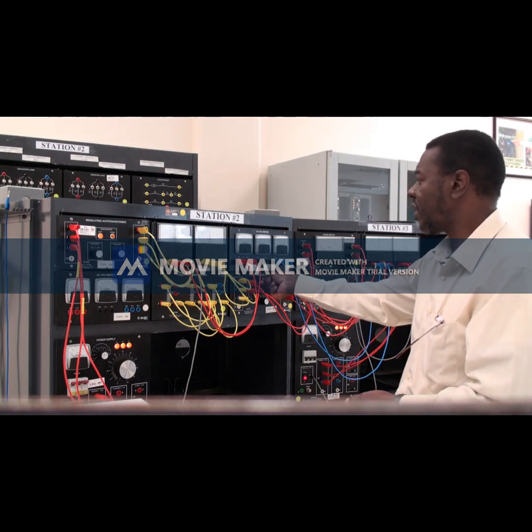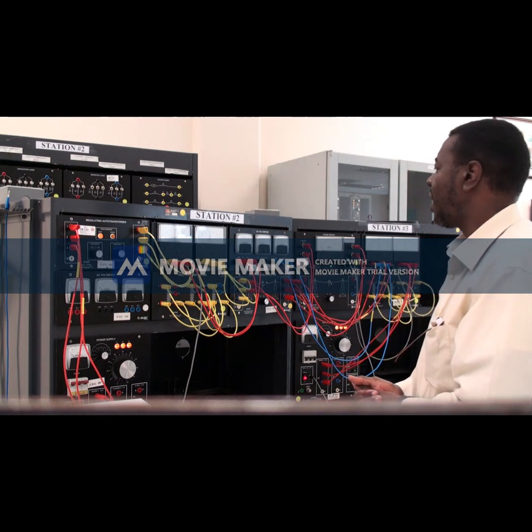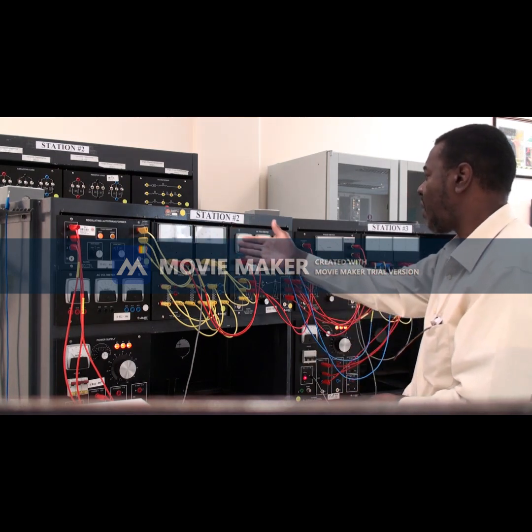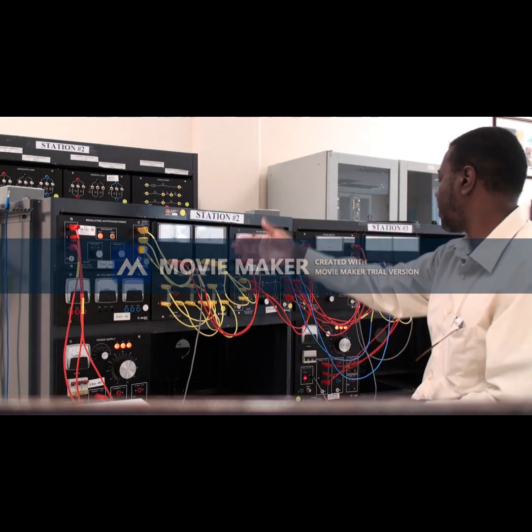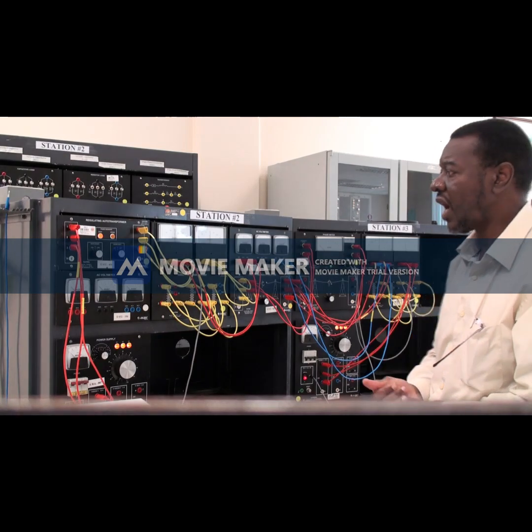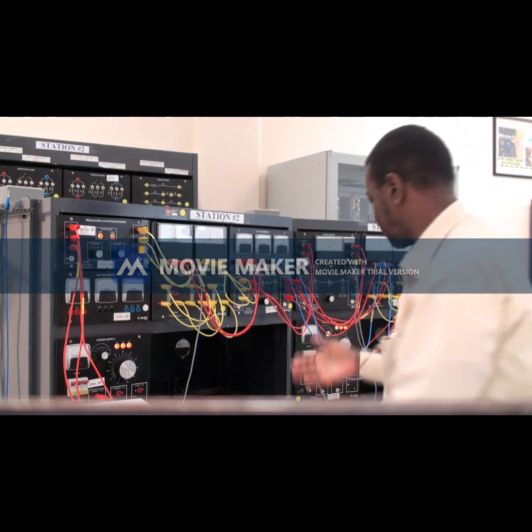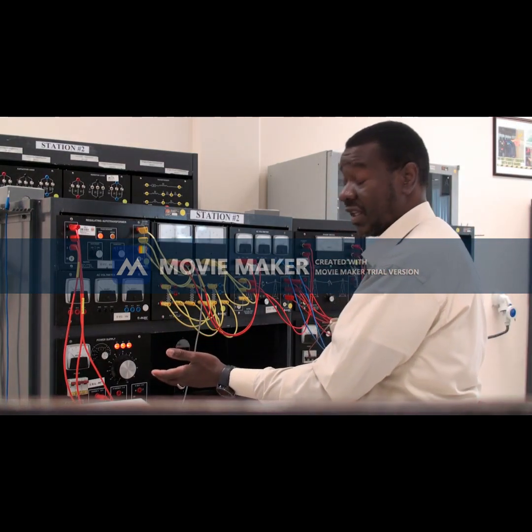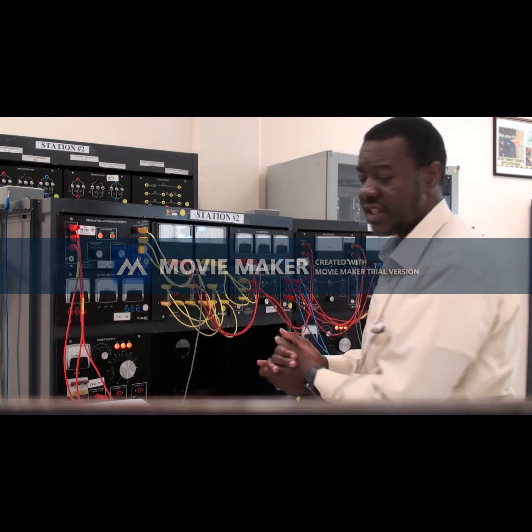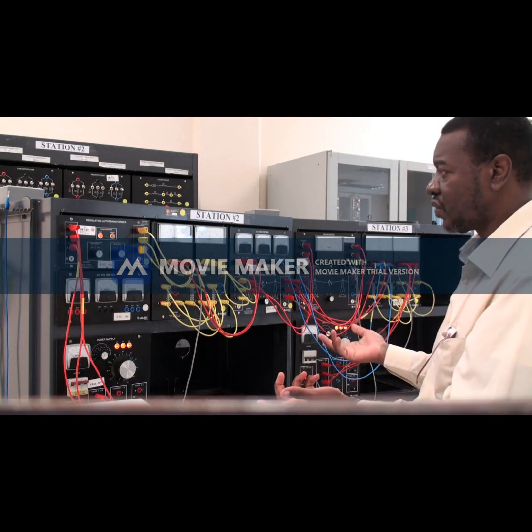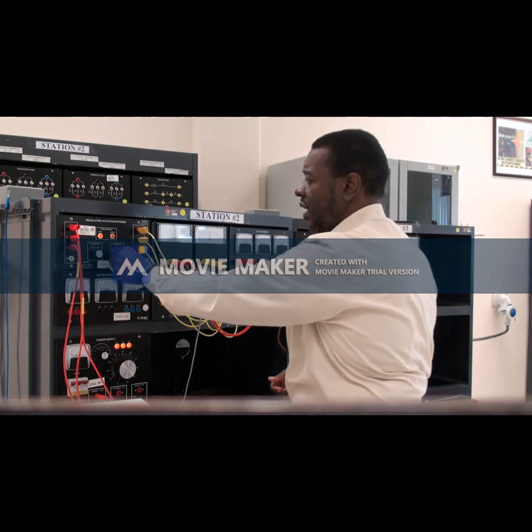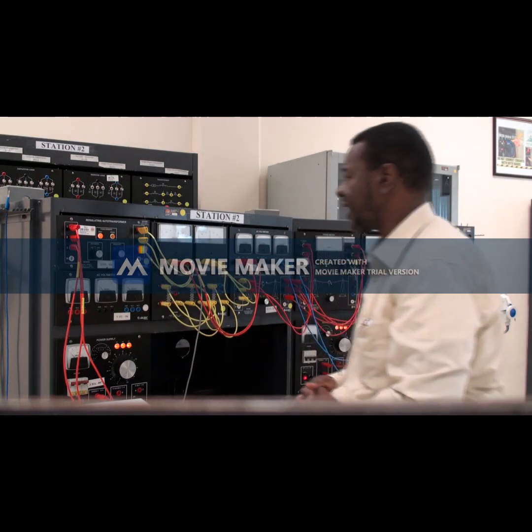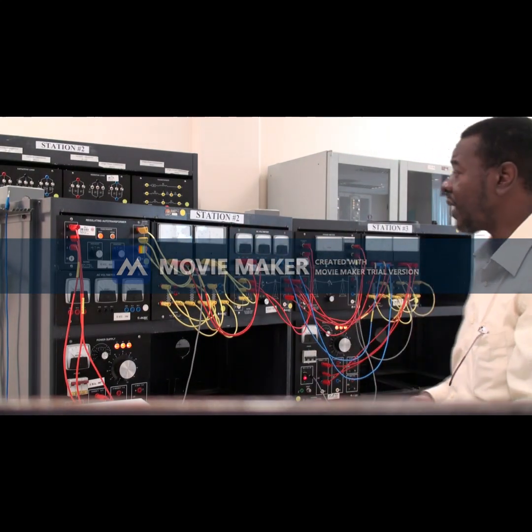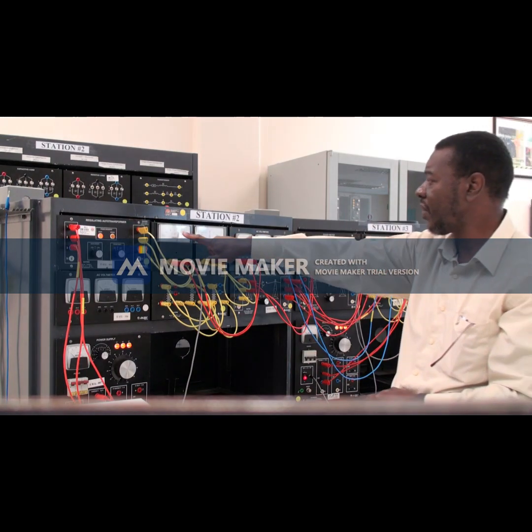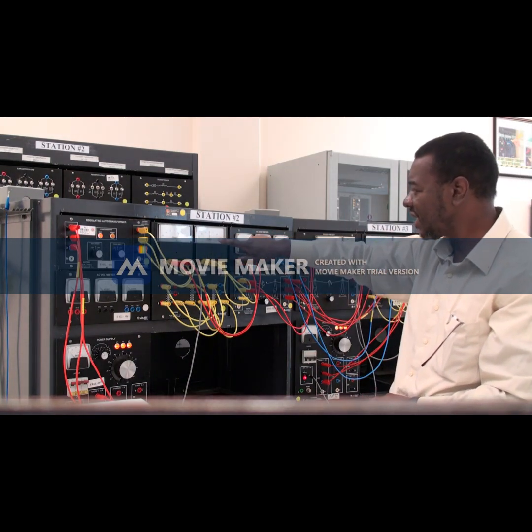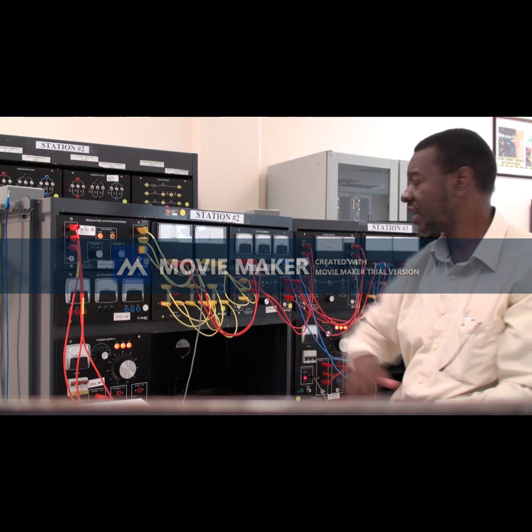So we'll switch on our transmission line. It's on now. Still the real power is 0, reactive power also is 0. And now, since we have both voltages at 220 volt, we want to change the angle between them and see what happens. So if we go to plus 15 angle, now we can see how the power is changing. Now we have real power here. We have almost 0 reactive power from station A.